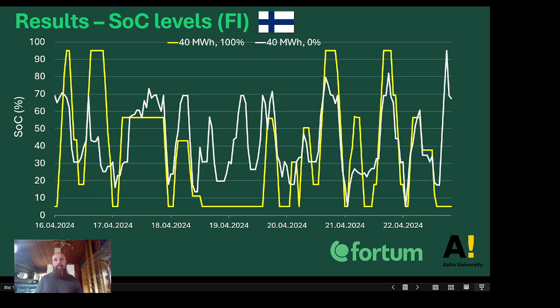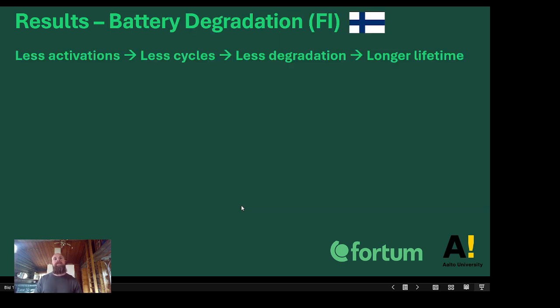As can be seen, imbalance management has larger activated volumes but less frequent activations, and the state of charge limits are reached more often with only imbalance management. The less activations you have, the less cycles you have; the less cycles you have, the less degradation you have, which then extends the lifetime of your battery.